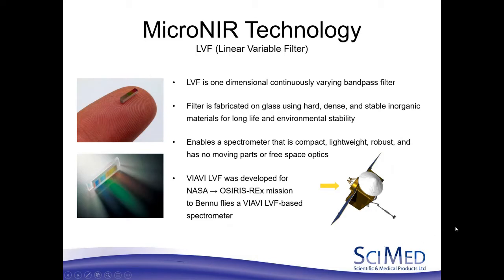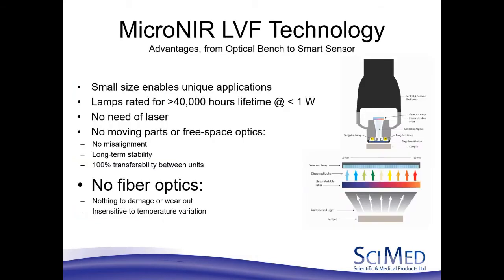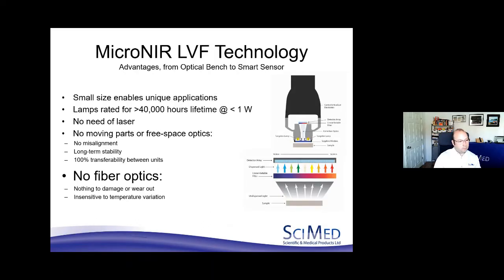So we're utilizing this technology. It's a small form factor, which opens up some unique applications. It has a very long lamp lifetime, greater than 40,000 hours, and there's no need for any laser or moving parts. The great thing about this is there's 100% transferability between units, so any method you develop on one system can easily be transferred to another. Also, there's no fiber optics, which can be expensive and tend to be affected by temperature variations.